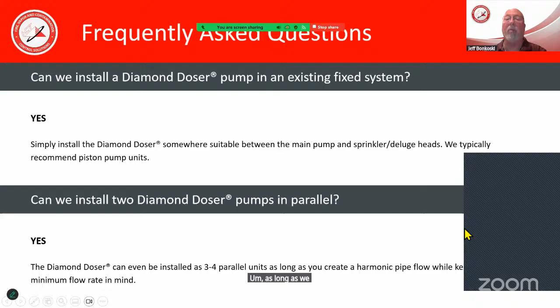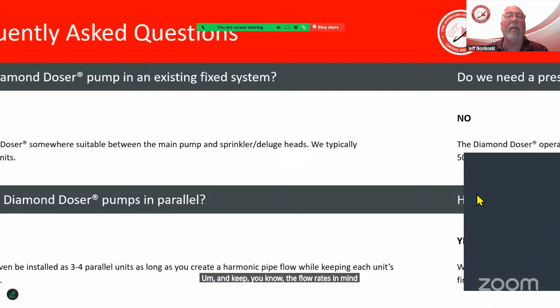Can two diamond dosers be installed in parallel? Again, the answer is yes, as long as we create the harmonic pipe flow and keep the flow rates in mind, things can be accomplished. As for a pressure tank to store the F500 concentrate, no, it's gravity fed. All we have to do is have that concentrate tank slightly elevated above the height of the diamond doser, usually on a pedestal of some sort, and it will be fine.